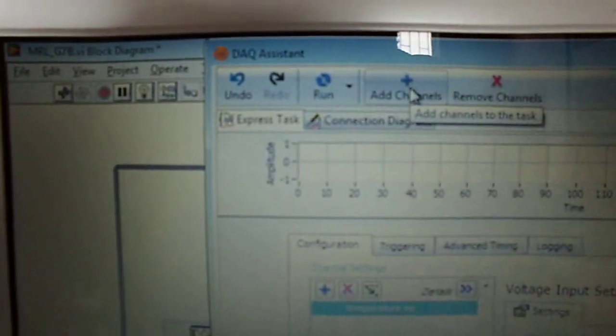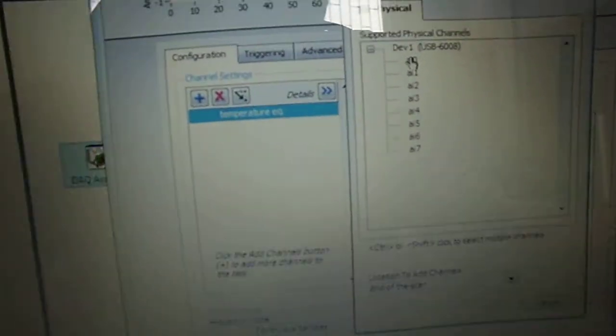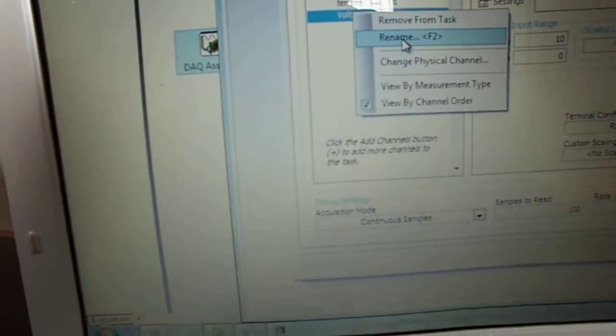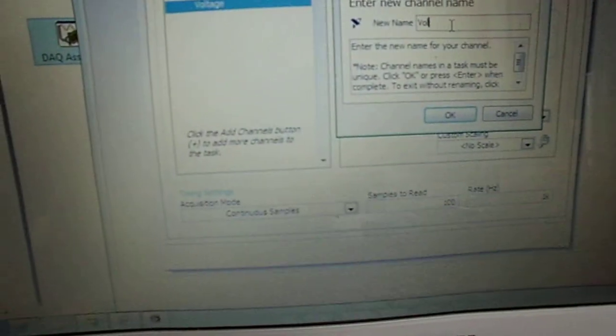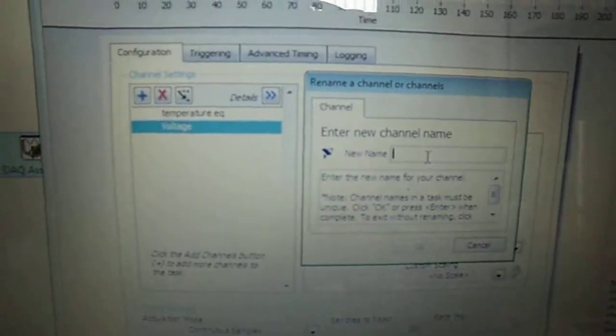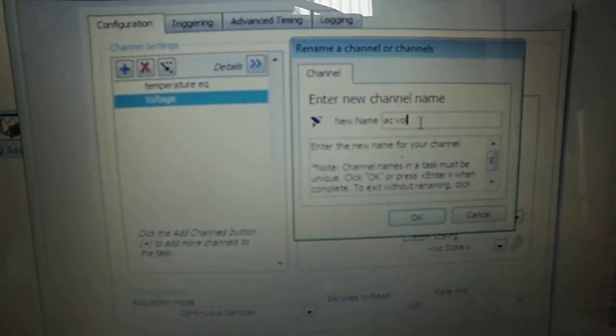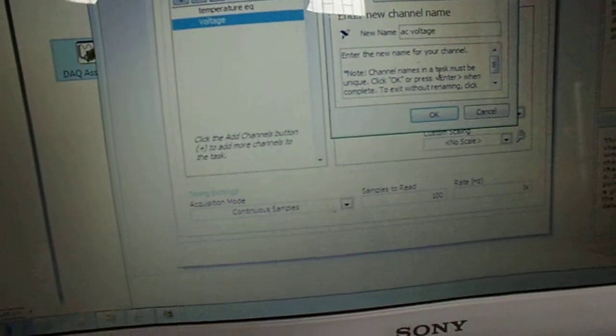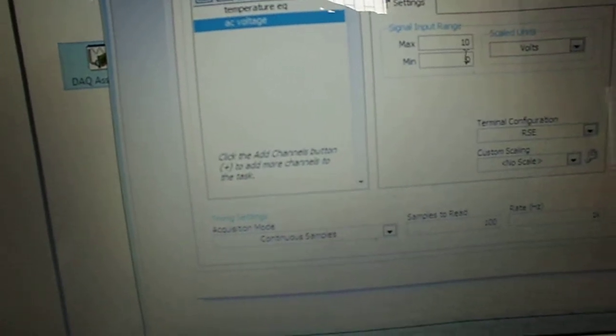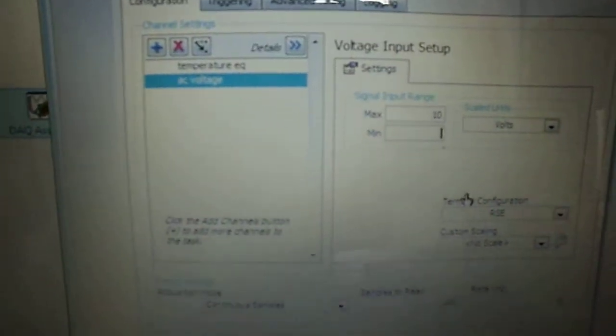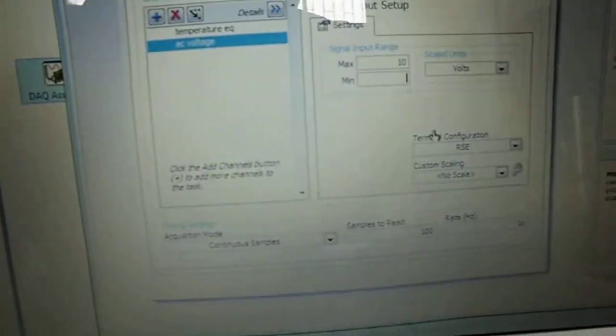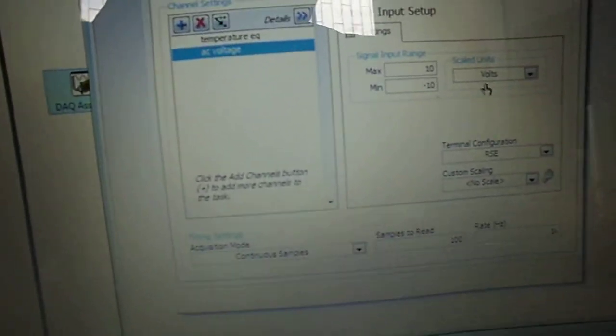We have two signals to analyze as an input. Click 'Add', decide voltage. We work with voltage, port number zero. Click OK and rename that. As I said, this is the AC voltage from the resistance. I put the name 'AC Voltage'. You can decide the name you want. Click OK. The maximum value is 10V and the minimum value — because I'm working with AC signals — I decide minus 10V as a minimum value.